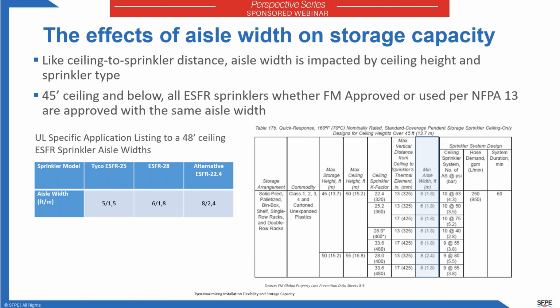When you get to 50-foot approvals through the FM data sheet, all the ESFRs that are approved by FM... when you get to 55 foot, there's again a difference in the aisle width approvals. The ESFR 28 is approved with an 8-foot aisle, and... is approved with a 6-foot aisle. And I'm going to talk in detail about what impact that has on storage capacity.